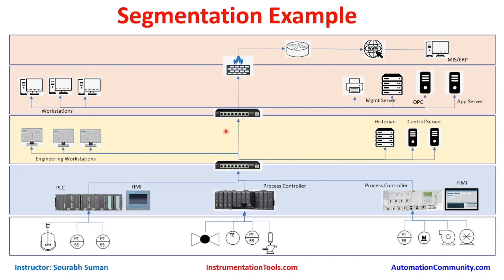Now let's look at this example. We are aware of this architecture — this is a Purdue model of a basic DCS. Here we have created one segment containing all our physical interfaces. At the next level we have PLCs, HMIs, and process controllers — these two levels together form one segment. Whatever communications go from this segment to another, we can put a firewall or a Layer 3 switch with access control lists here to control communications from these devices.